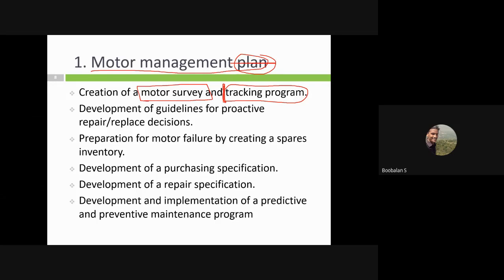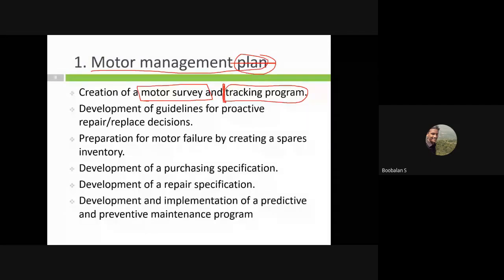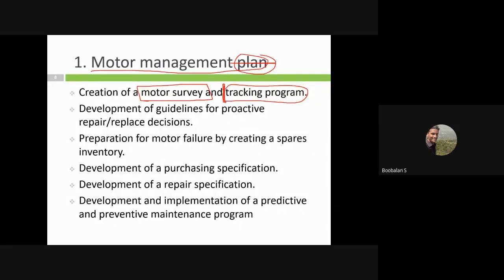We need to check phase-to-phase voltage, phase-to-line voltage, and current flow in each phase. For example, for a 5 HP motor on a 3-phase power supply, around 7.5 amps of current is drawn. We need to check the per-phase current, whether it's around 7.5 or lower, like 6 amps. The current consumed across the three phases R, Y, B should be equal. If R phase draws 6 amps, Y phase should also draw about 6 amps. Otherwise, consider an example where R phase consumes 10 amps and B phase only takes 3 amps.